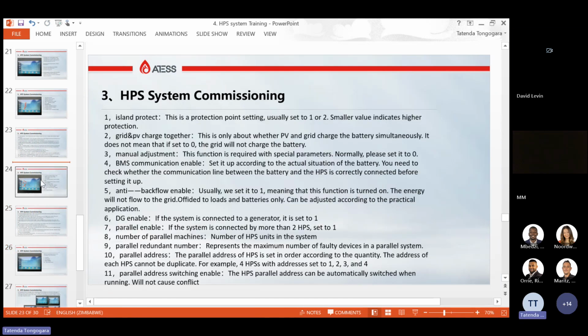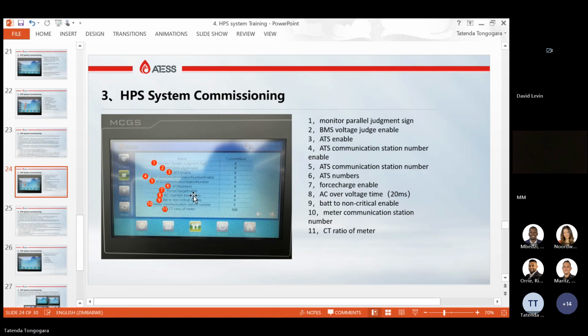Okay, so AC overvolt time. In the event that there is an over voltage in your circuit, this is the time taken by the HPS to react to an AC overvolt issue. If the sampling board detects an over voltage, this is the time it will take. You can set it to 4, which is the value that comes with the inverter, and then you can set it to 6, but I advise you to leave it at 4.